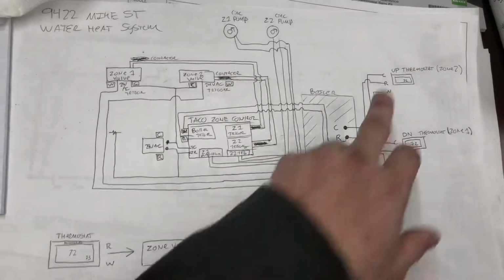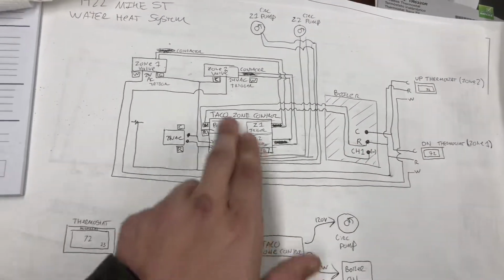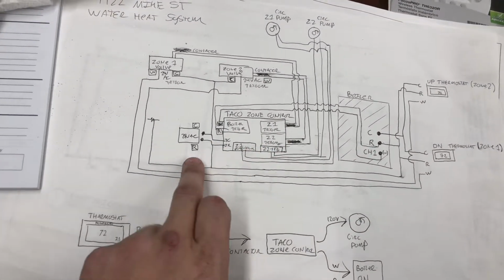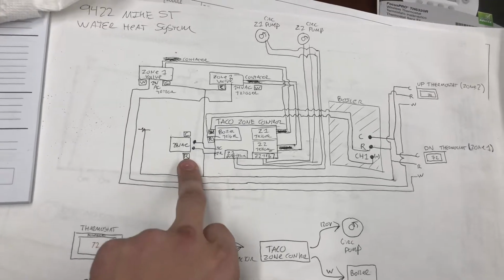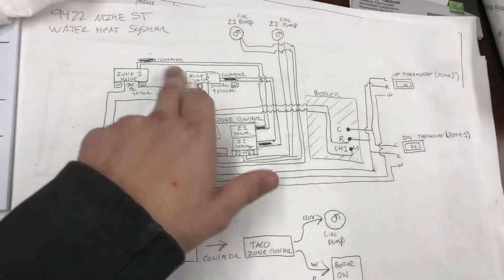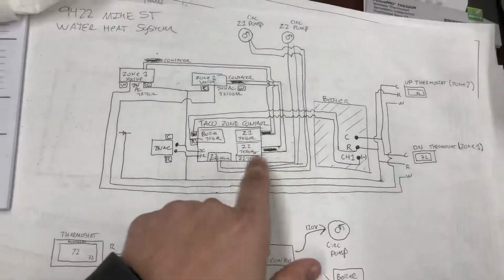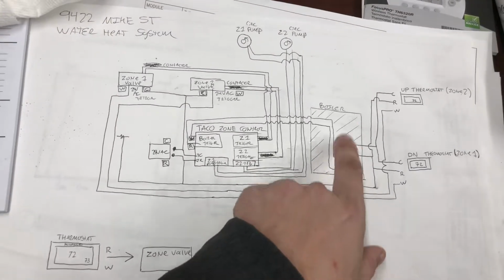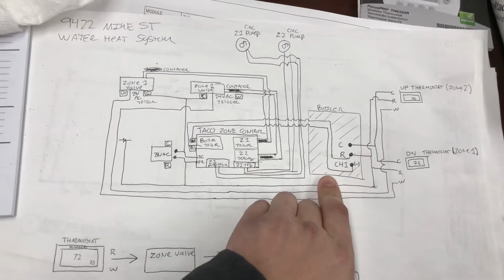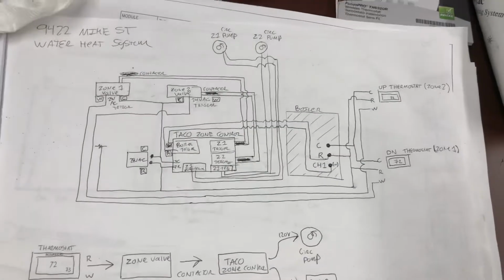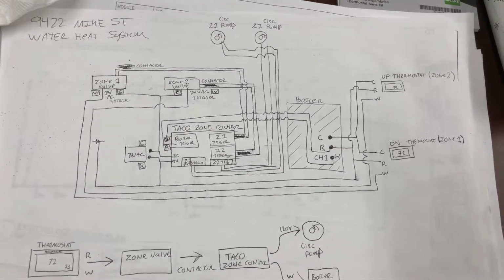So circ pumps, thermostats, boiler, the taco. This is a separate 24 volt AC transformer. I did this just to power the valves and the thermostats without kind of taking down the transformer that's actually integrated in the TFT Trinity boiler. It's just kind of a good insurance. It should make it last a lot longer.